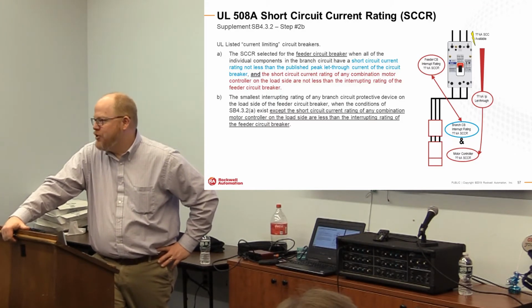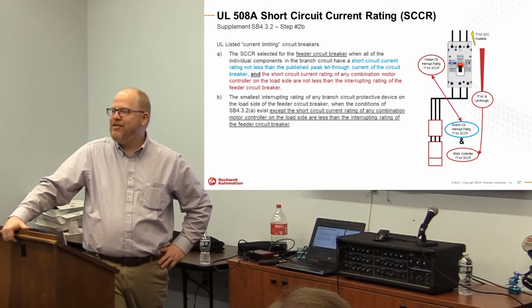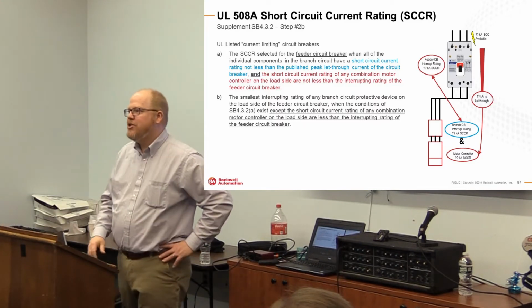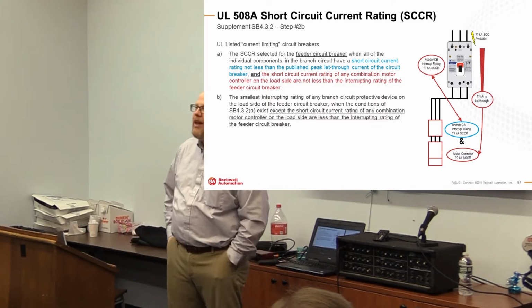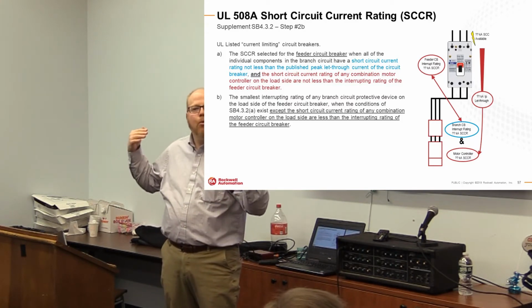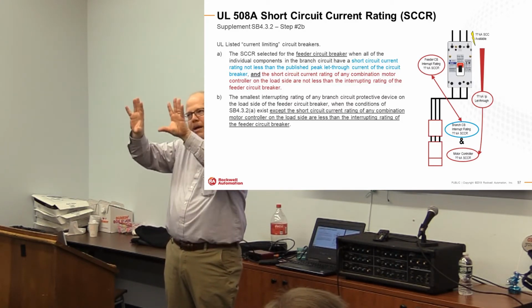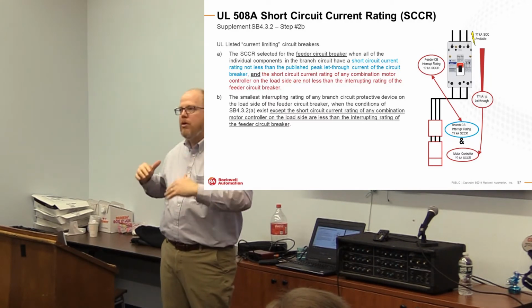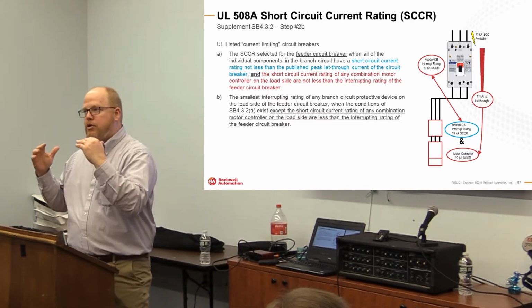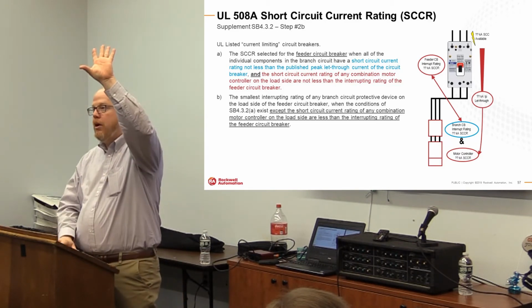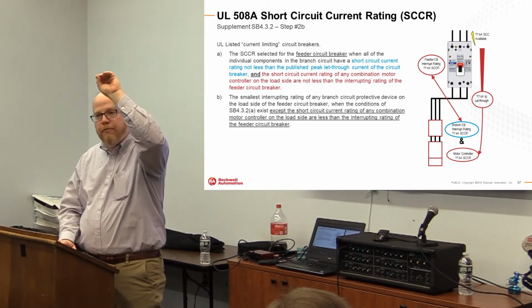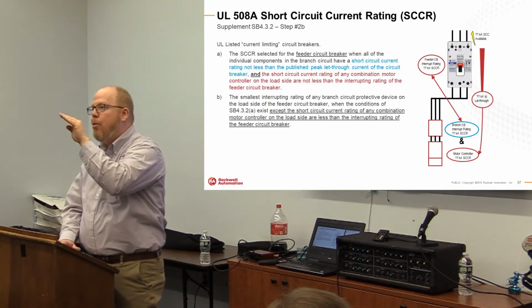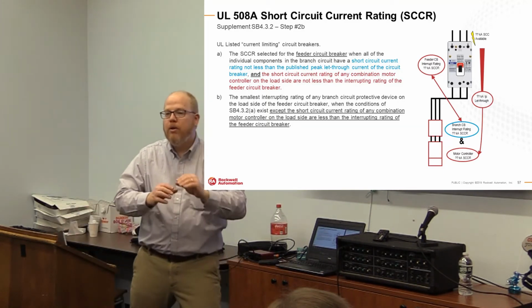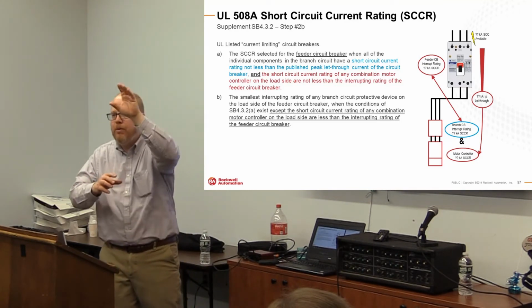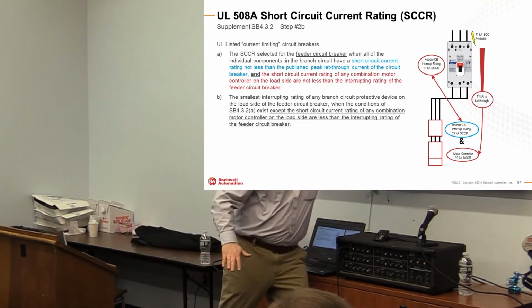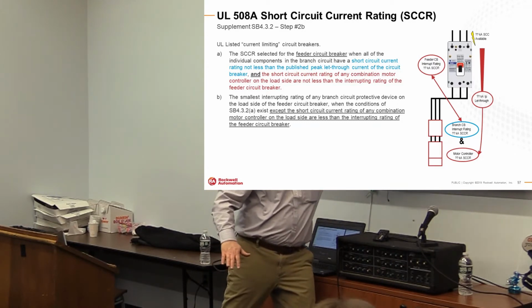I don't expect you to consume all this information right now. The lack of silence that I always get during these presentations is because you just don't know what I'm saying. And sometimes you need time for this to sink in. What I would encourage you to do if you're trying to understand this is go back to this slide and read the color code, and so I'll just work through it for you. So the short circuit current rated selection for the feeder. Okay, so we're talking about feeder current limiting. In order to determine the feeder current limiting capability, we need to zoom down to the branch, and there could be multiple branches, remember, right?